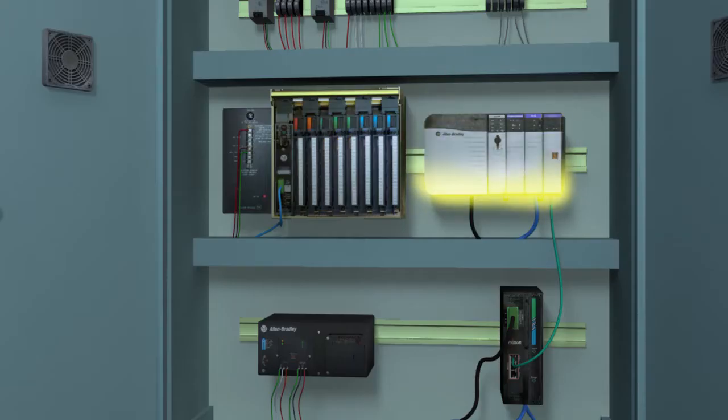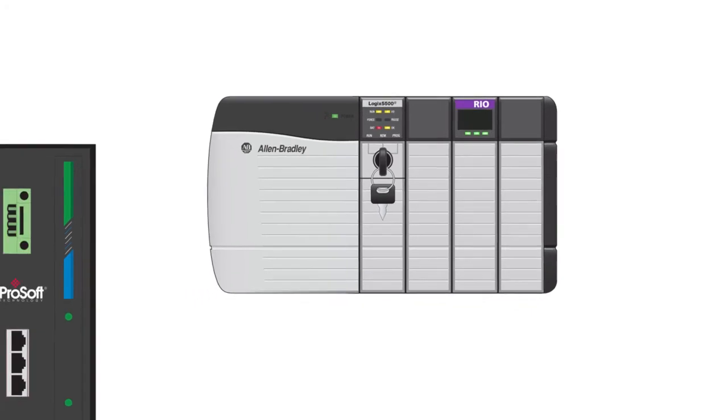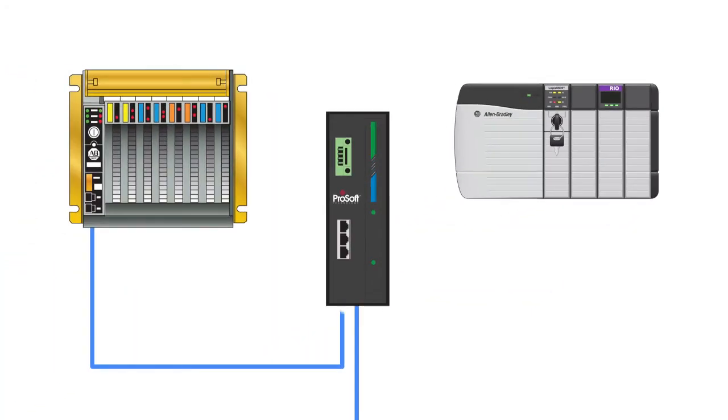A ControlLogix system can be configured and the PLC5 program converted while your remote I.O. system continues to run as normal. When you have your program converted, a 1756 RIO module can be used in the ControlLogix system to take control of the remote I.O. devices during regularly scheduled downtime.